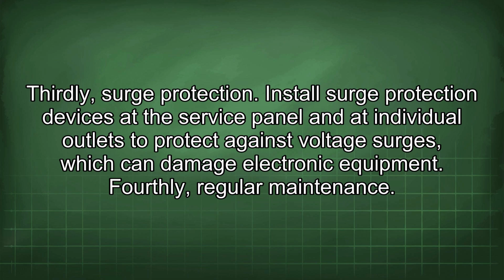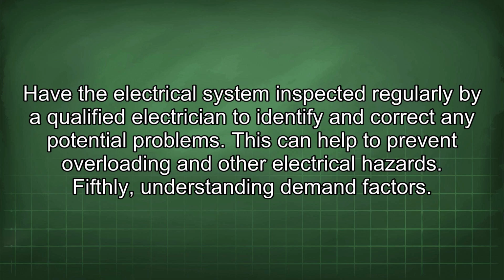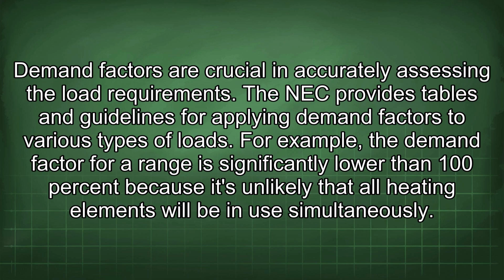Thirdly, surge protection. Install surge protection devices at the service panel and at individual outlets to protect against voltage surges which can damage electronic equipment. Fourthly, regular maintenance. Have the electrical system inspected regularly by a qualified electrician to identify and correct any potential problems. This can help to prevent overloading and other electrical hazards. Fifthly, understanding demand factors. Demand factors are crucial in accurately assessing the load requirements. The NEC provides tables and guidelines for applying demand factors to various types of loads. For example, the demand factor for a range is significantly lower than 100% because it's unlikely that all heating elements will be in use simultaneously.